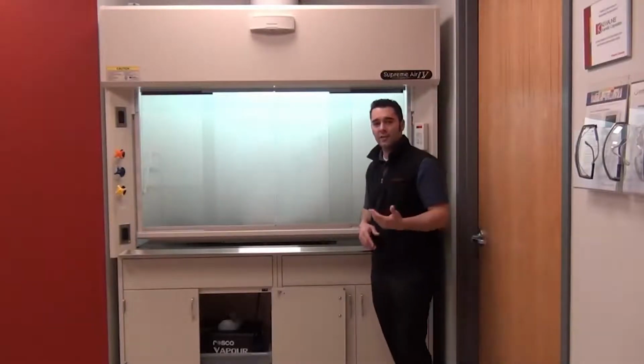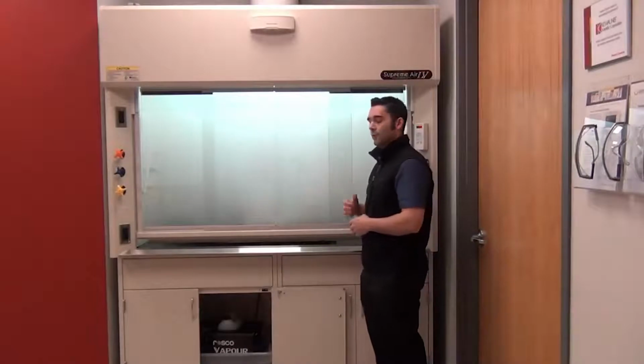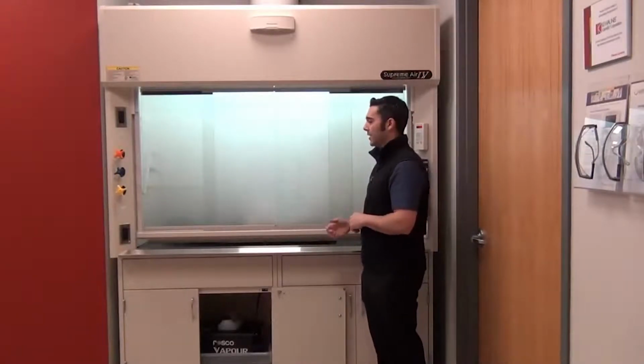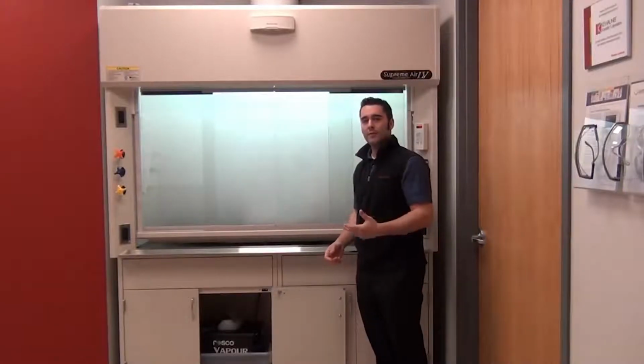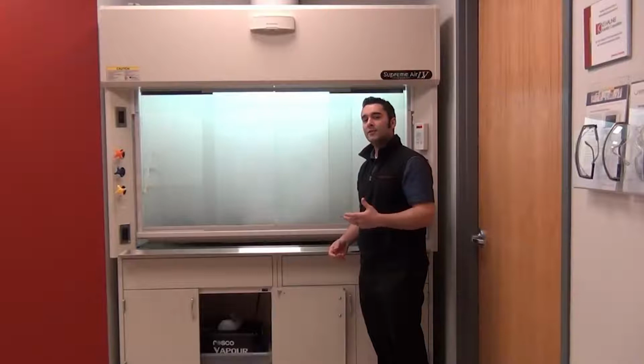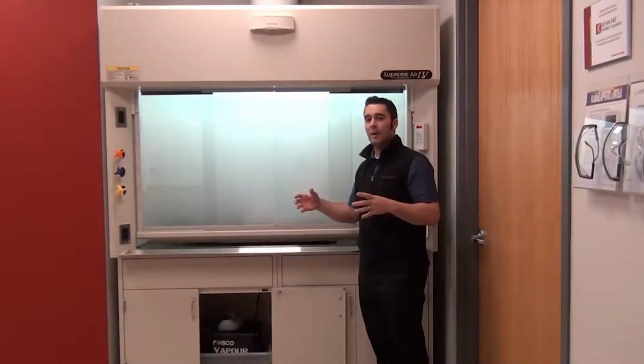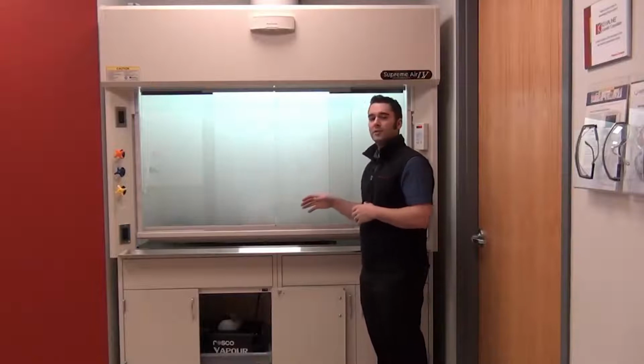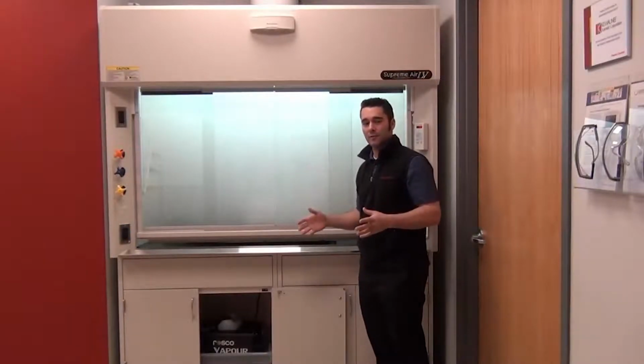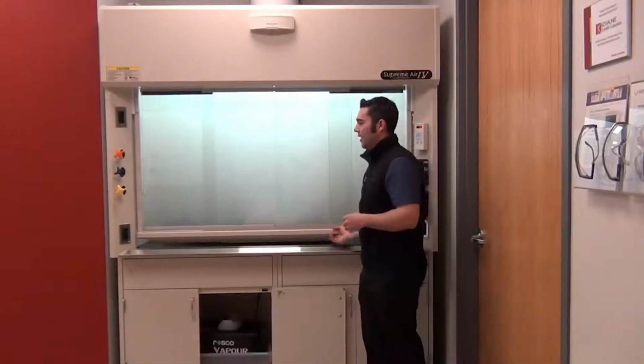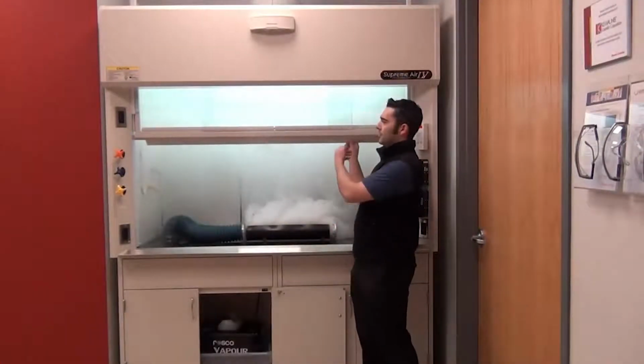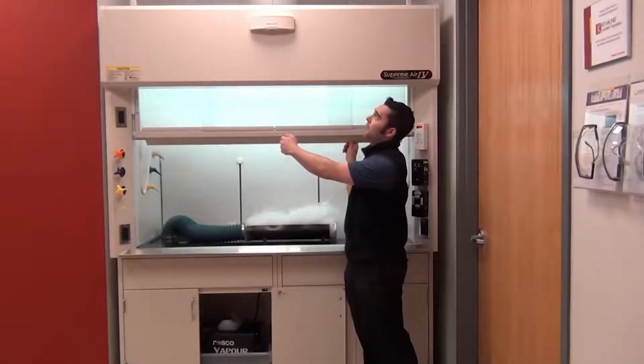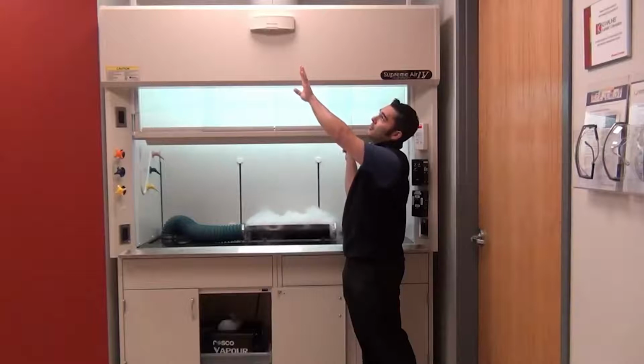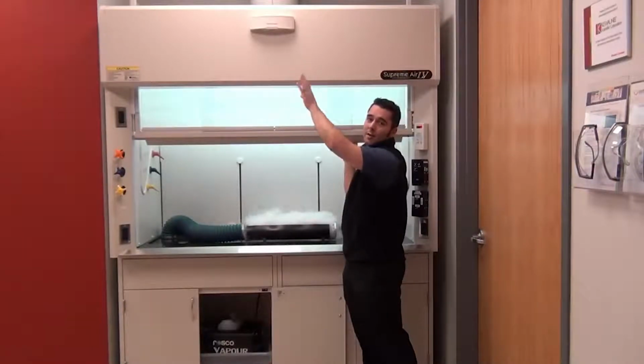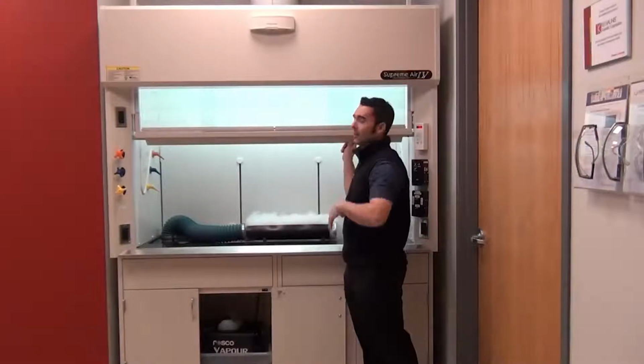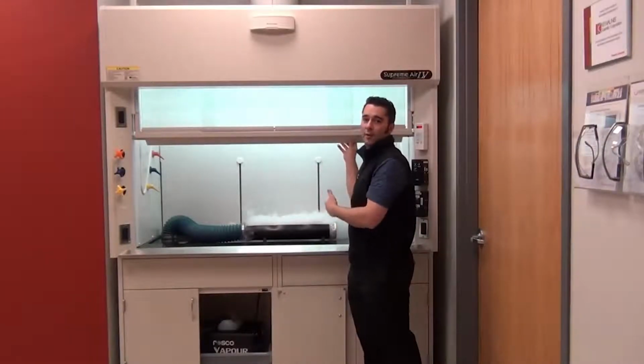I can also introduce a 6 second speed of response into this fume hood as well. So same type of delay where I'm stepping up the command over 6 seconds. And again, if you're using a flow measurement type device, even if you have a fast actuator on it, it's still going to take longer than that actuation time before that device is going to stabilize. So this is going to simulate if you had something that was a 6 second flow measurement device, which really doesn't exist either. But if I'm using something that has a 6 second speed of response, you can see now there's a lot more loss of containment here on the face of the hood. And I don't know if you can see it on the video, but there is a great loss of containment coming out the top of this hood, because that valve is taking 6 seconds to respond when I'm moving the sash at the same rate I was previously.